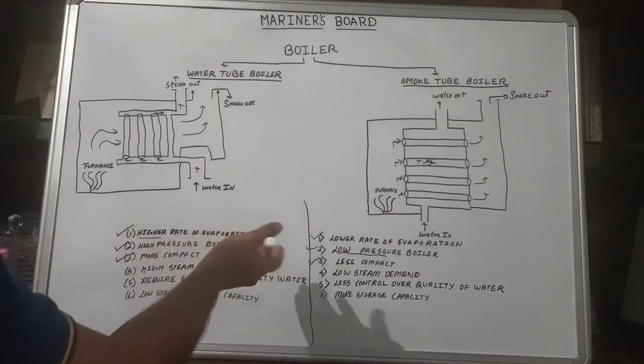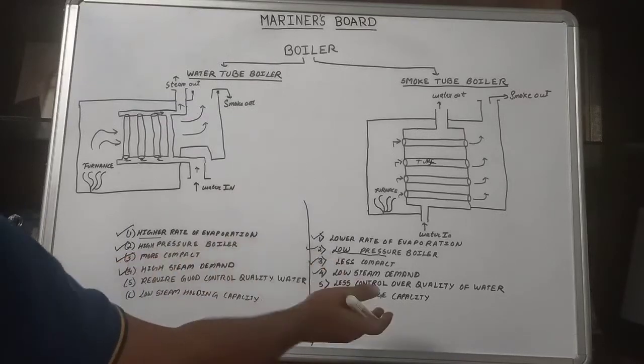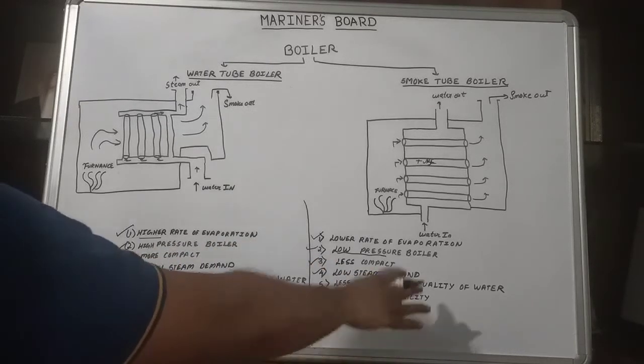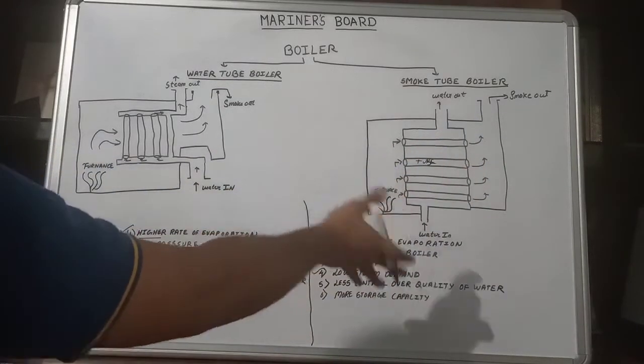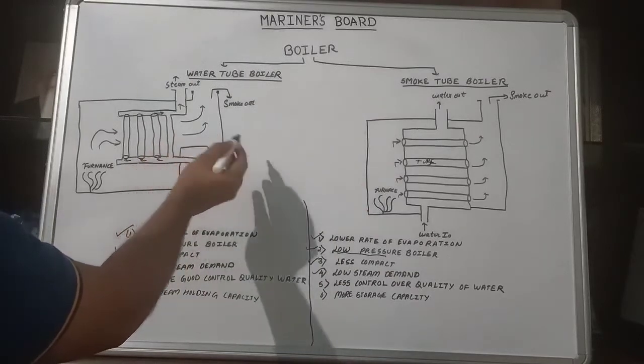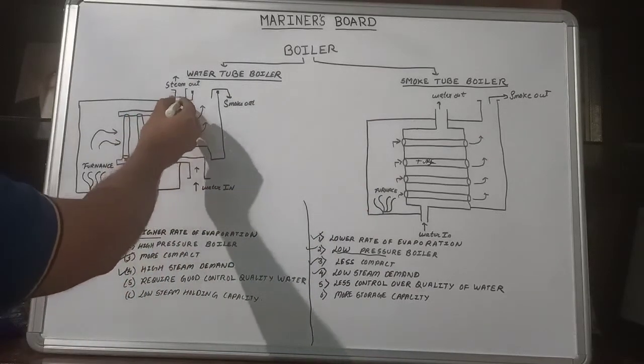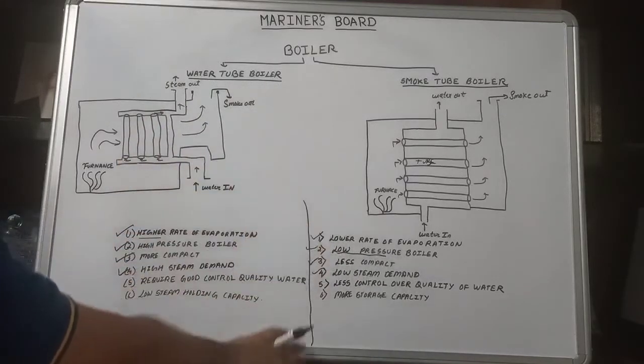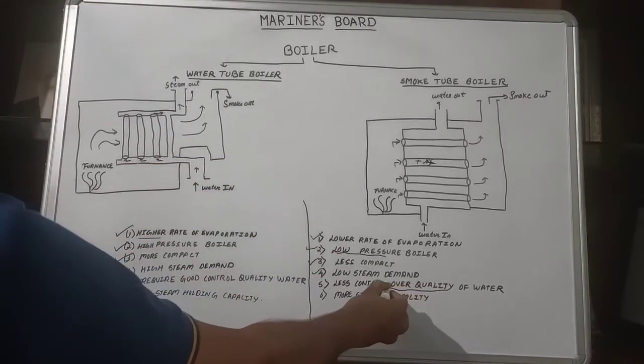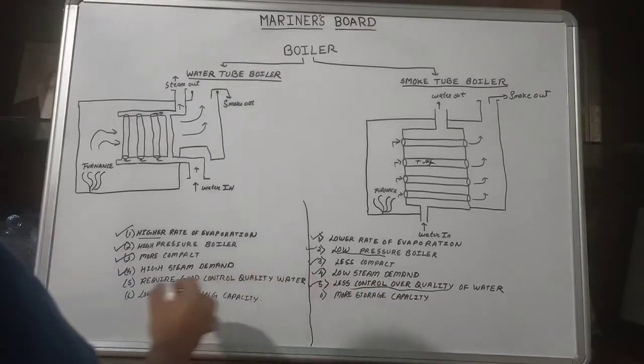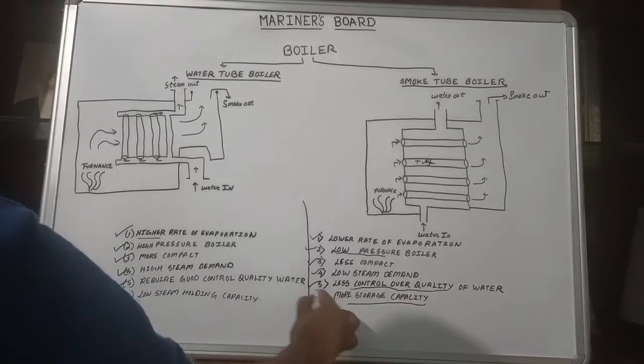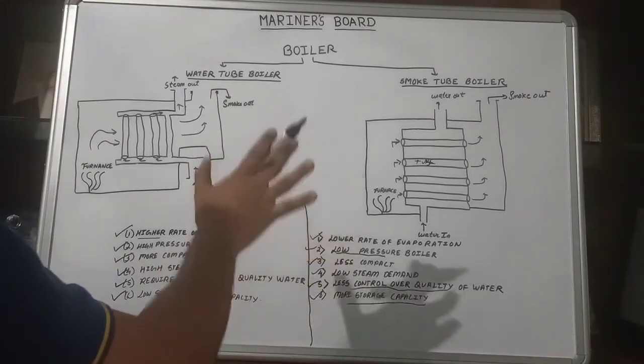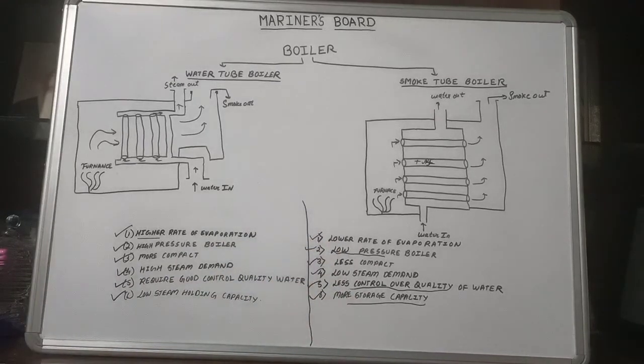In a smoke tube boiler, since water is not flowing through the tubes, we do not need much control over the quality of the water. Whereas in a water tube boiler, water flows inside the tubes, so it is very necessary to have good control over water quality. Additionally, the smoke tube boiler has more storage capacity for steam, whereas the water tube boiler has less steam storage capacity.